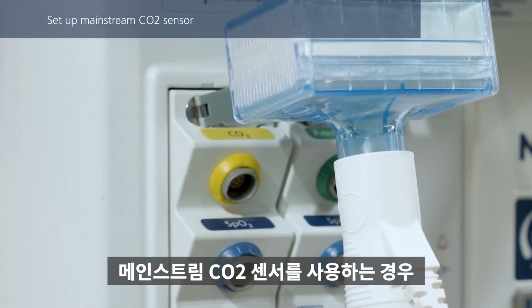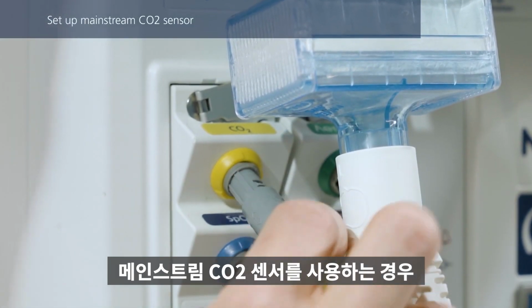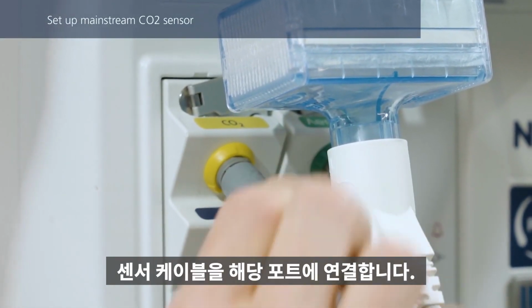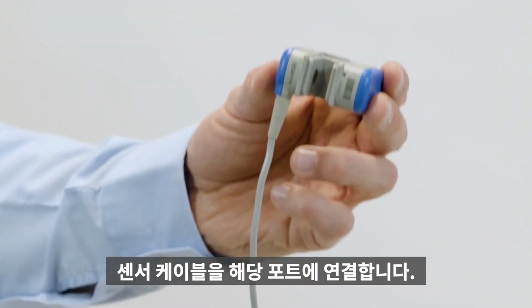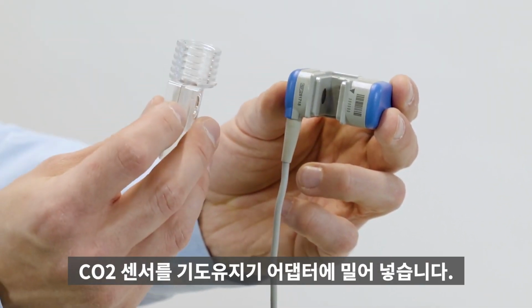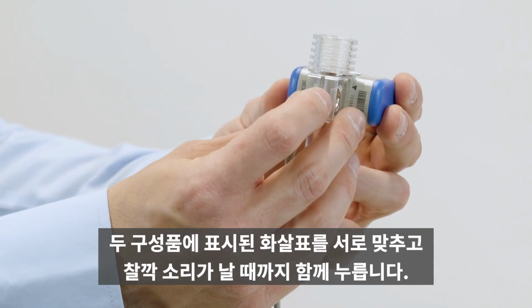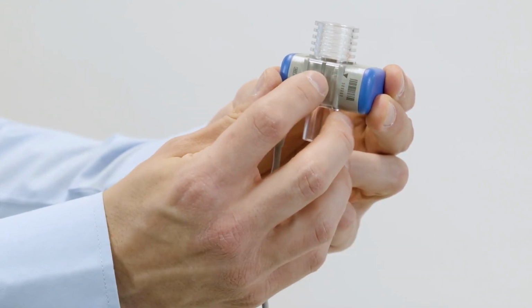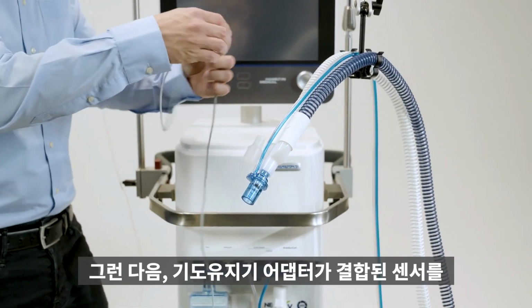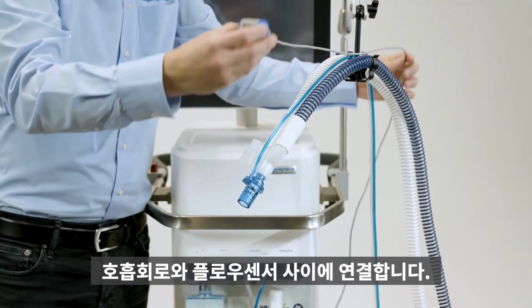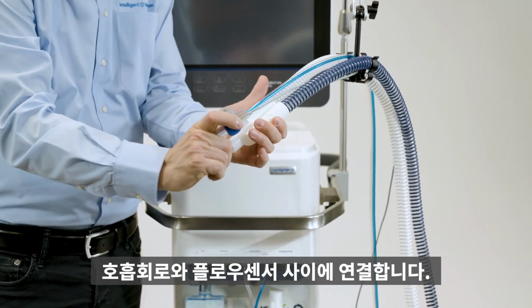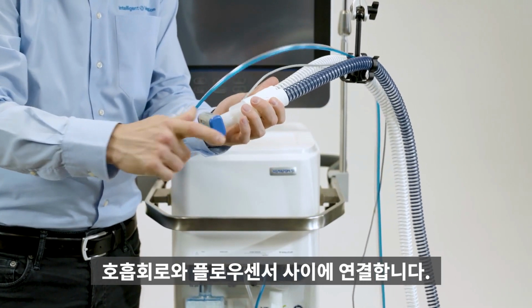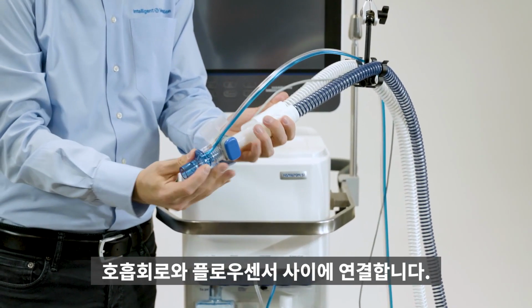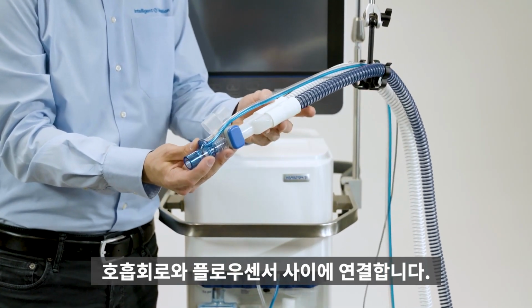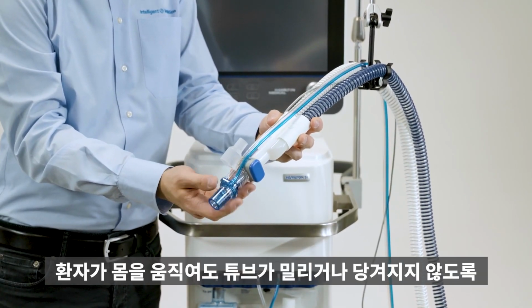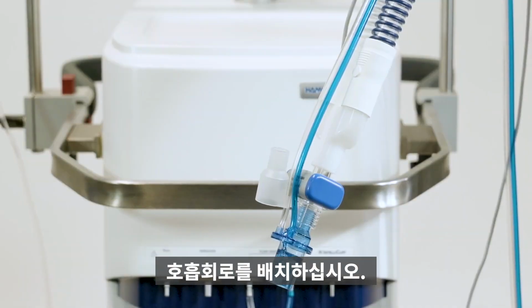If you are using a mainstream CO2 sensor, connect the sensor cable at this point to the corresponding connection port. Slide the CO2 sensor onto the airway adapter. Align the arrows on both components and press them together until you hear a click. Then connect the sensor with the airway adapter between the breathing circuit and the flow sensor. Position the breathing circuit in such a way that the tubes will not be pushed, pulled, or kinked if the patient moves.